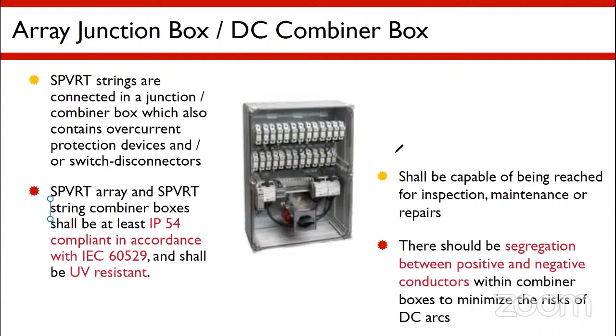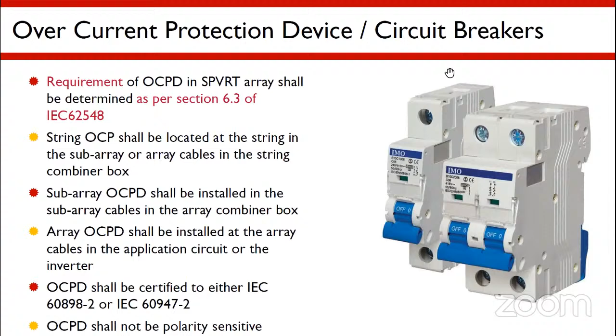So these are the overcurrent protections, like how we've seen the SPDs. These are the MCBs. The MCB is also rated for DC and AC. For DC applications, you can use the DC MCBs, and the DC MCB will have ratings of 12 amps, 16 amps, 20 amps, then 40 amps, 50 amps, up to 63 amps. For AC, the MCBs go up to 120 amps.